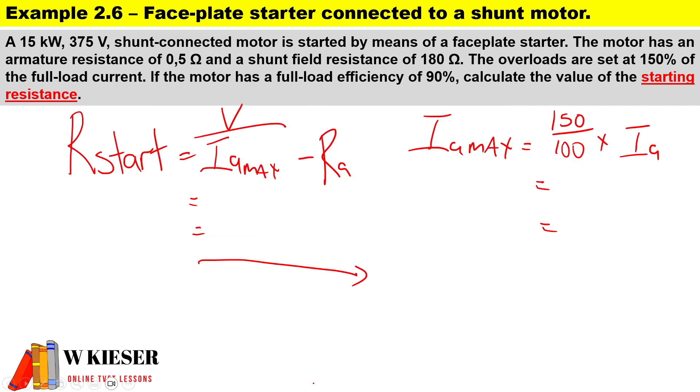Now we want to protect this motor. To work out the maximum current that the armature can reach, we take our overload, which is 150 divided by 100, times the armature current. The armature current was 42.362. Therefore, Ia max will be equal to 63.543 amps.